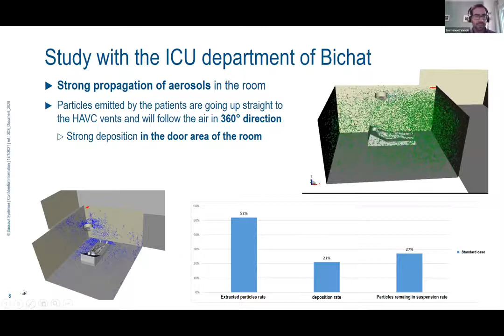And as a result, what do we have in this situation? We can see that after 1 minute of simulation, 50% of all the aerosols emitted by the patient are extracted by this HVAC system. We have a deposition on surfaces of around 20%. So you have in the blue some hot points of aerosols at different locations of the room, which leads at the end to a remaining particle suspension of a bit less than 30%, which is already quite good. But then the idea was to try to improve this situation a bit.